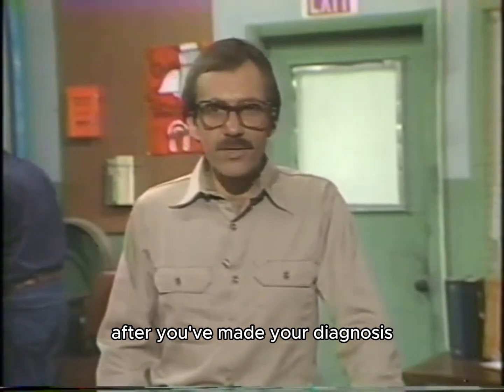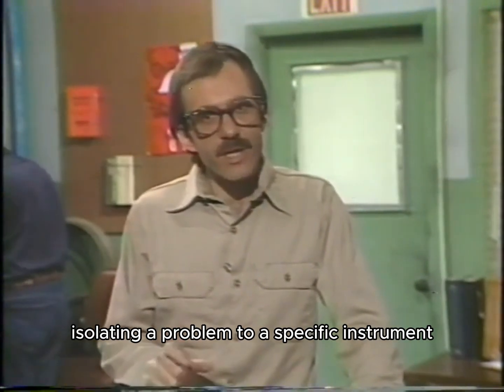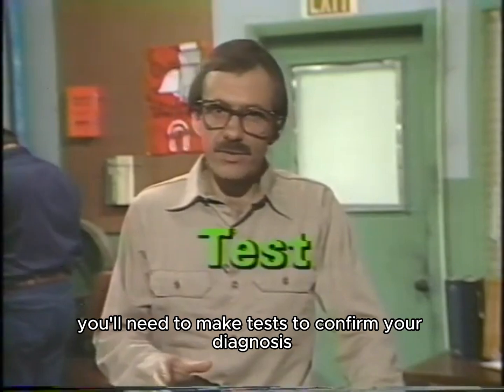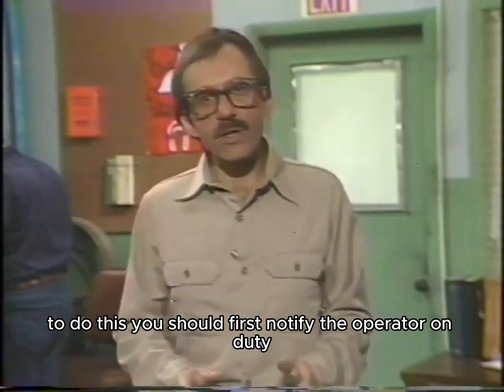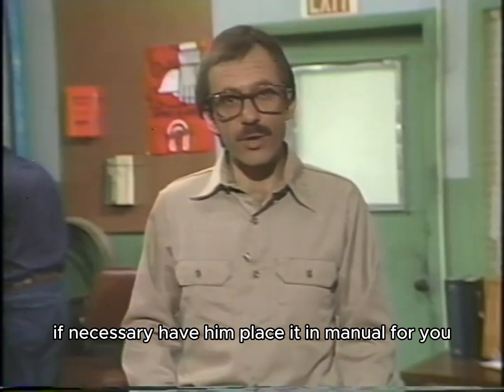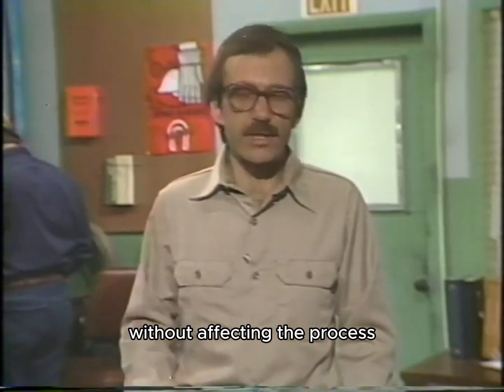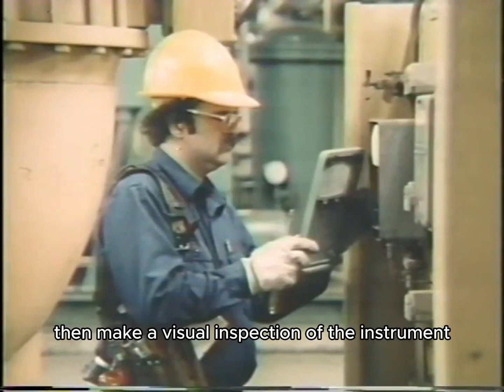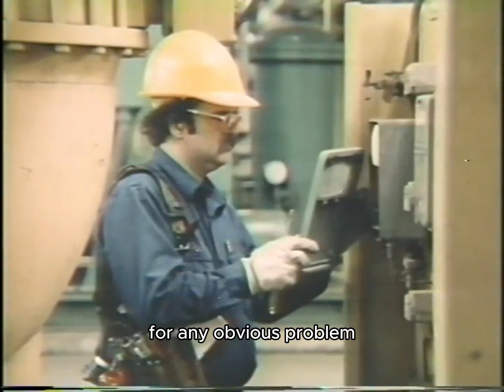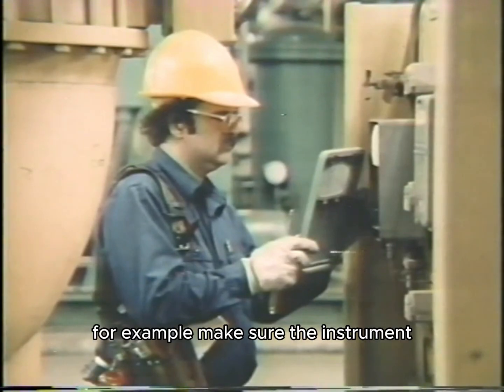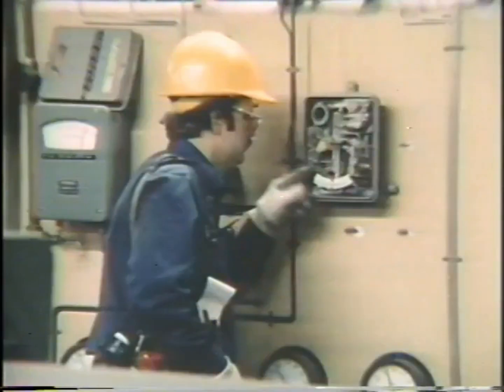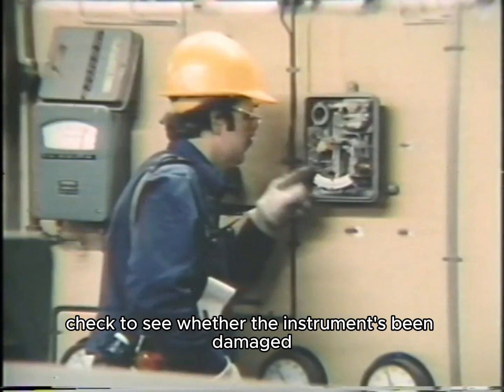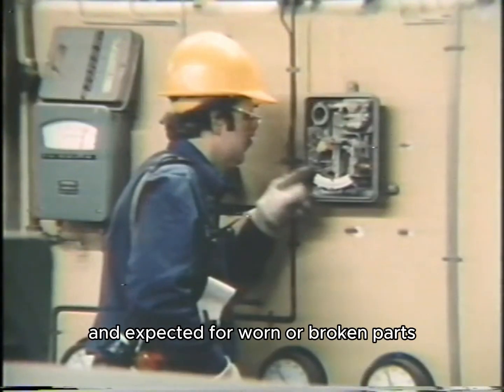After you've made your diagnosis, isolating the problem to a specific instrument, you'll need to make tests to confirm your diagnosis. To do this, you should first notify the operator on duty that you're going to be working on the system. Let him know what instrument you're going to be testing, and if necessary, have him place it in manual for you so that you can work on the system without affecting the process. Then make a visual inspection of the instrument for any obvious problems. For example, make sure the instrument air supply hasn't been shut off. Check to see whether the instrument's been damaged, and inspect it for worn or broken parts.